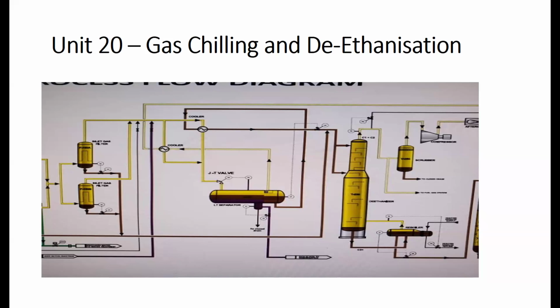When you come into the plant, if it was a plant tour, you will see that most of the manifolds, the entrances to the vessels, are icy. The reason is that within that unit it is minus 33 degrees Celsius at normal operating pressure, due to the Joule-Thomson effect, the cryogenic effects that we have all learned in our thermodynamics classes. So this is pure thermodynamics going on here. One key thing I would like to stress is we have a shell and tube heat exchanger system. There are so many types of heat exchangers around, which I'm sure you have worked on before.